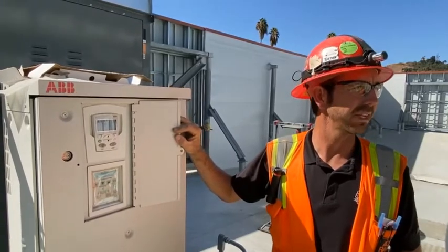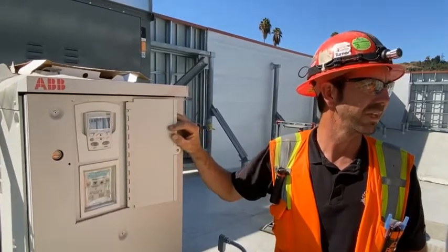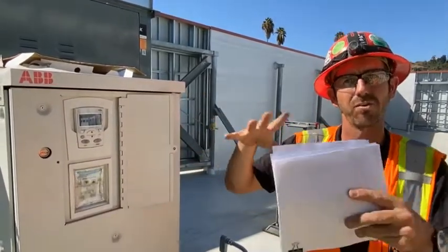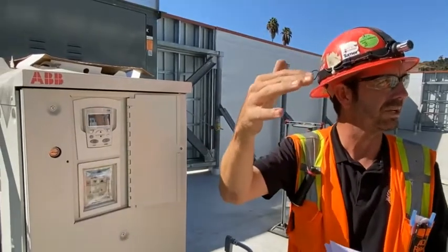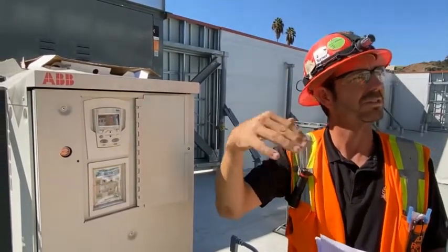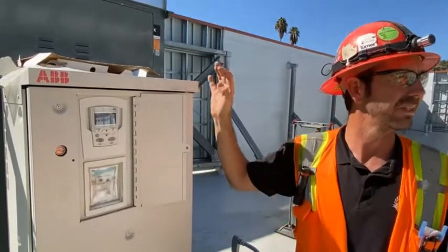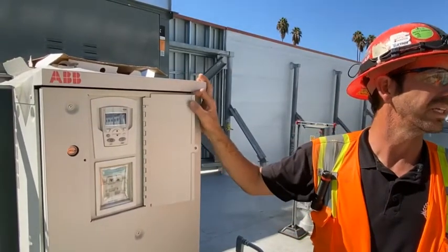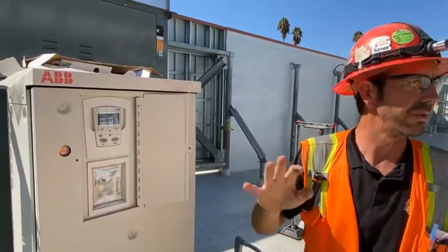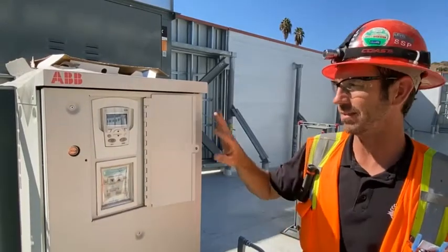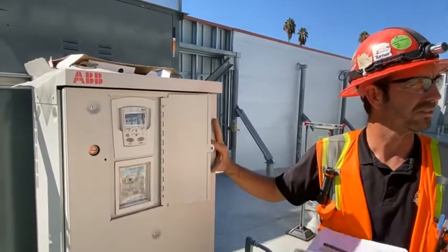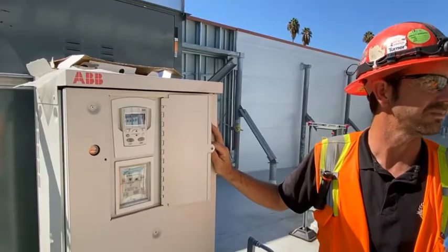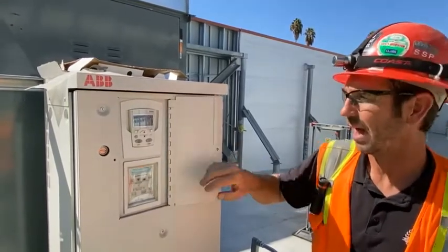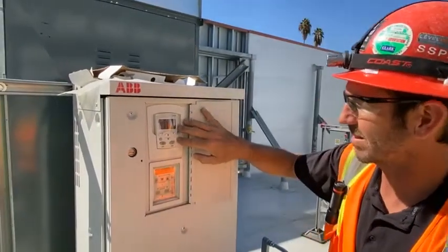There's a temperature sensor, I believe, in the Ansul system, that if the temperature in this ductwork over that hood rises to a certain predetermined temperature, it will turn on the fan to maintain that temperature. The Ansul system was provided by the electricians, and they should be able to give you the better on-off points on that. But this fan is being turned on and off through a start-stop command through the Ansul system, okay? I believe it was 47 hertz.